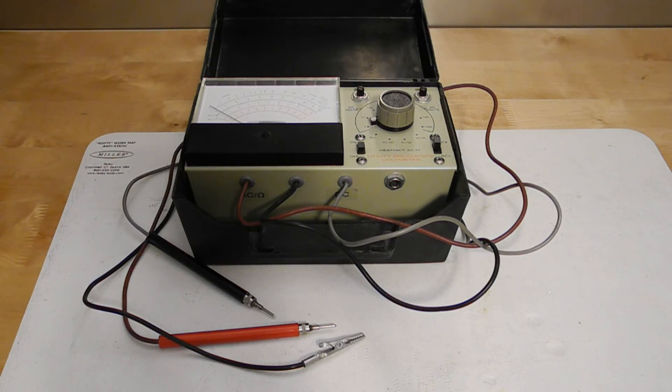It has a high input impedance to minimize the effect of loading on the circuit under test. The input impedance is 11 megaohms for DC and 1 megaohm for AC.